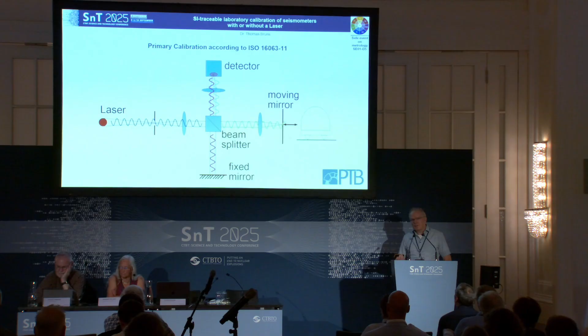And with that, you can calibrate or calculate the motion by calculating displacement, velocity, acceleration, and you have a primary realization. This is how it looks in reality. Here we have a seismometer on a 1.5 meter peak-to-peak shake table at PTB. And you see in the back where the green points are, on this small rectangular front side of a device, this is the laser interferometer.